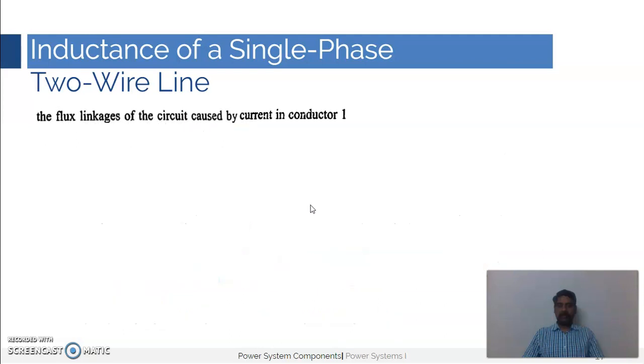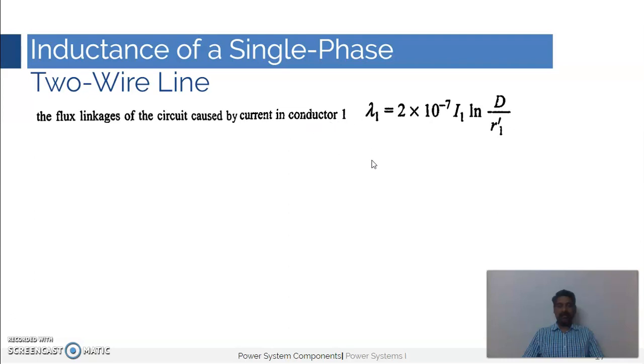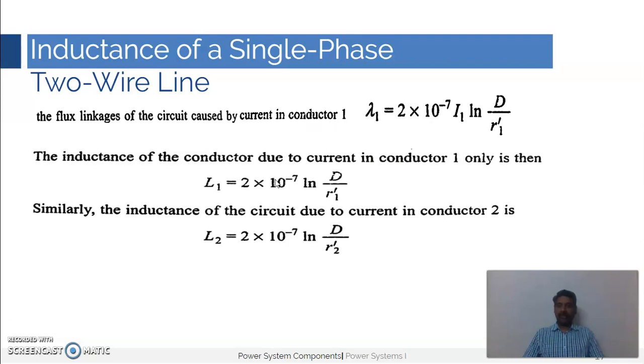With these assumptions we can easily write the flux linkages using the same equation discussed in previous videos. The flux linkages of the circuit caused by the current in conductor one alone can be written as: λ1 = 2 × 10⁻⁷ × i1 × ln(d / r1'), where r1' is the geometric mean radius of conductor one.